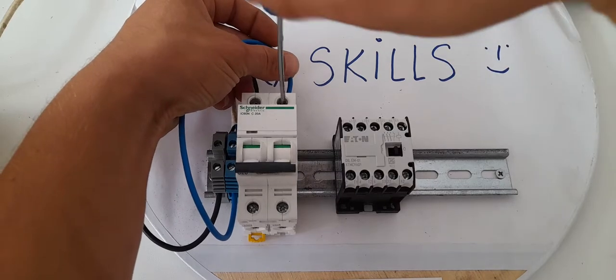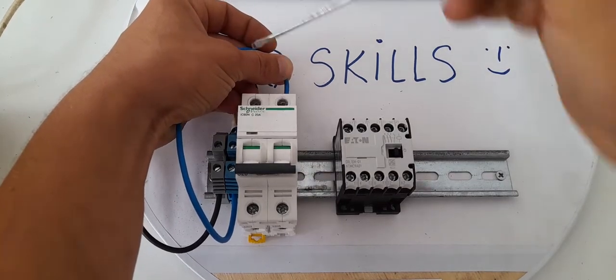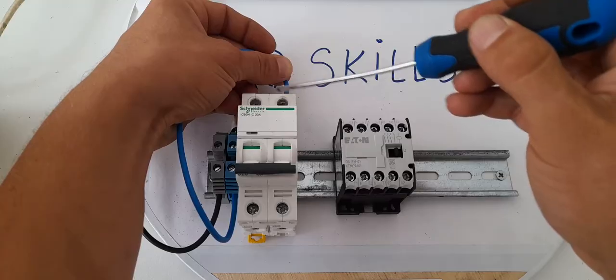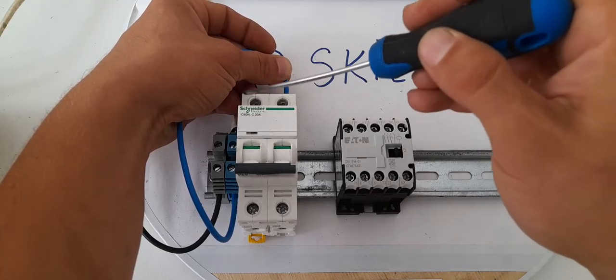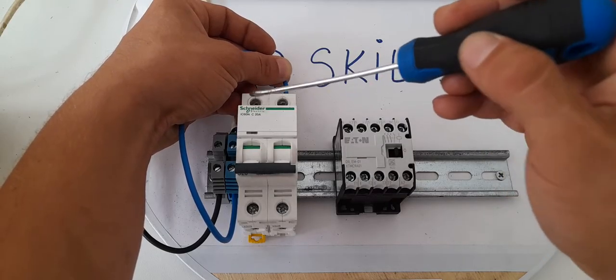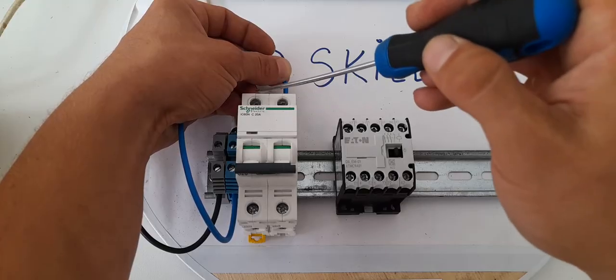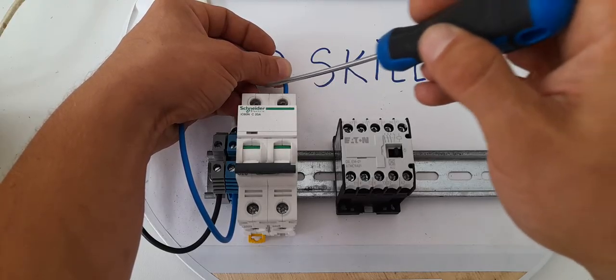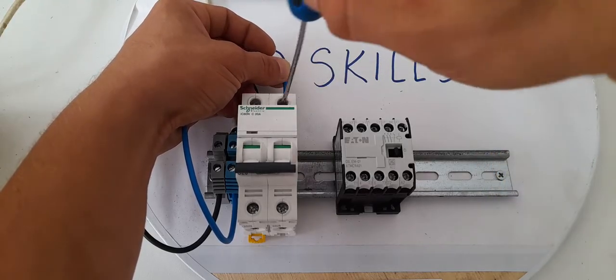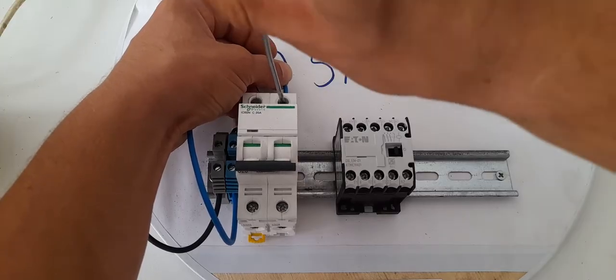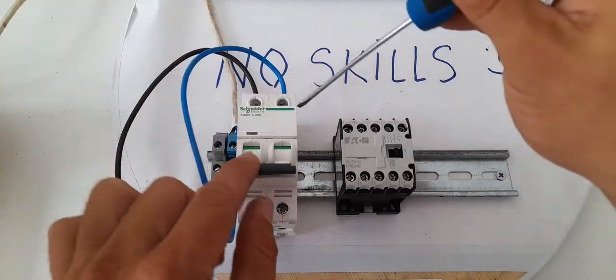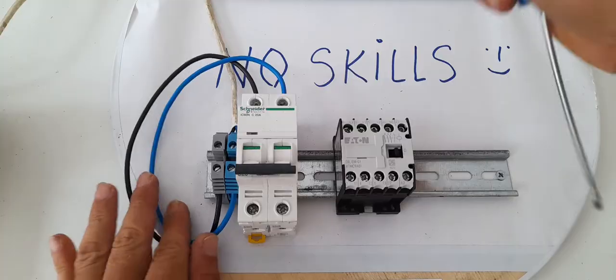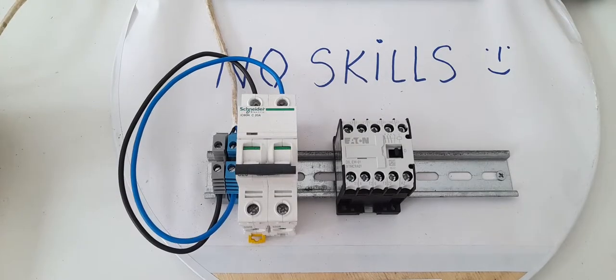And we're going to connect the neutral as well. You have to bear in mind, if it's rated N on here or here, you have to connect the neutral in the right position. This is a Schneider C20 2P, or two poles. Doesn't matter where you're going to connect it, so it's not going to make the difference. But if it's rated N anywhere, you're going to put it there. Alright.